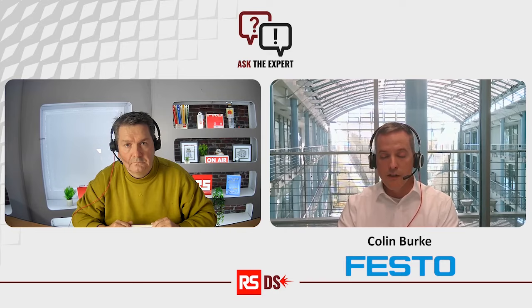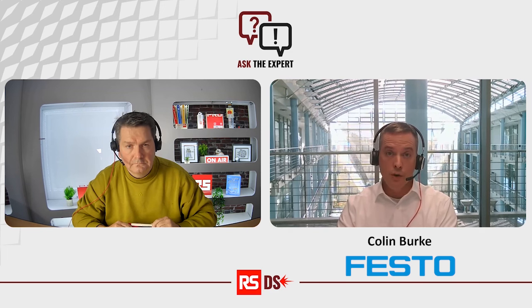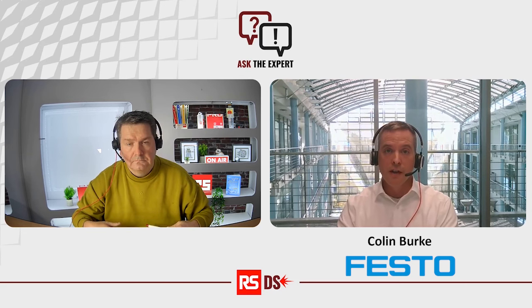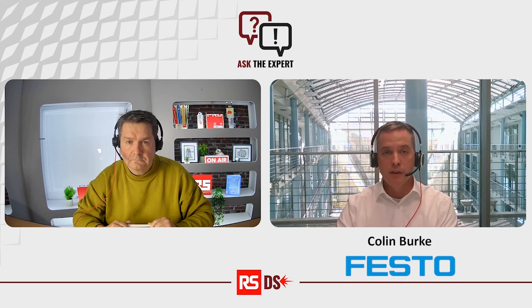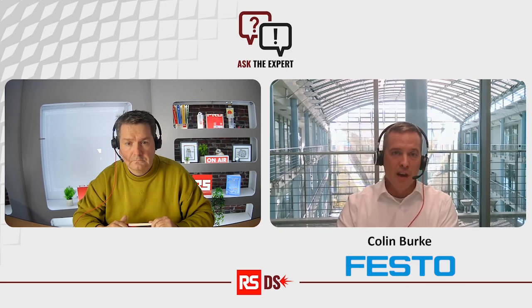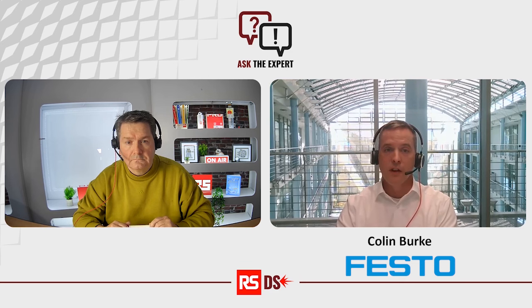So it's relatively simple using Automation Suite to either via the type code or the part number, you type in what it is and it'll pull the data. So you tell what's connected. If we're looking at a CMMT servo drive, for example, you tell what's connected to it. You'll have a certain cable, because we also know the losses over the cable. You'll have a certain motor. Hopefully, the customer will also take our mechanics, the gearboxes, and you can also tell it down to what it's going to do. And it'll take all that data, and in a few clicks, you've then got the control parameters.